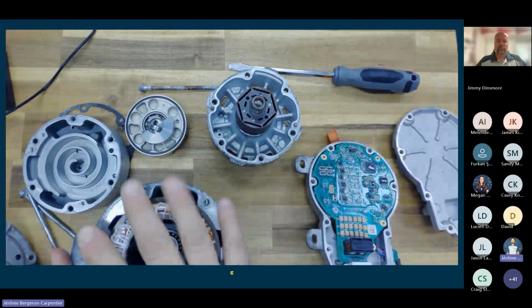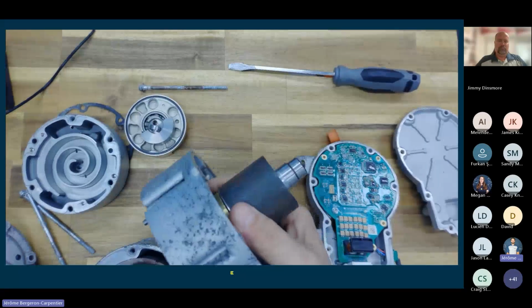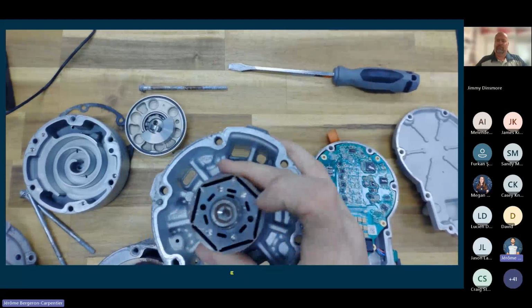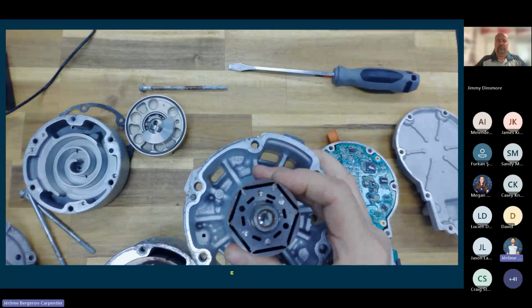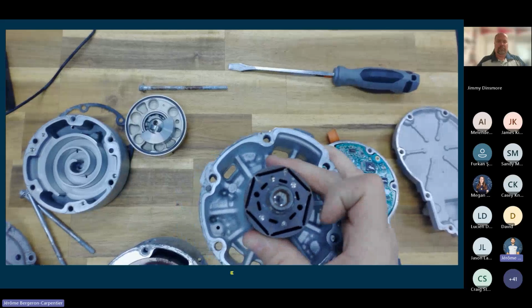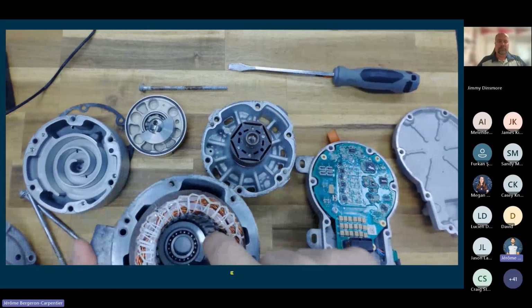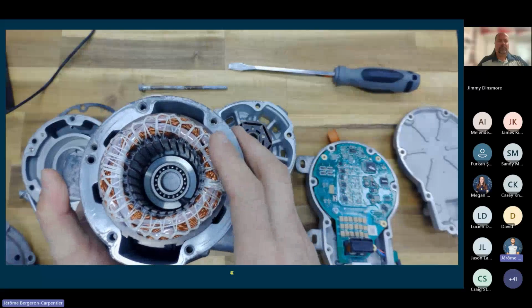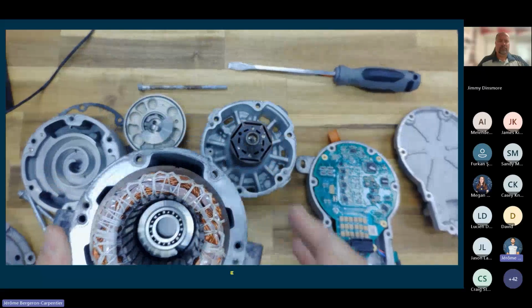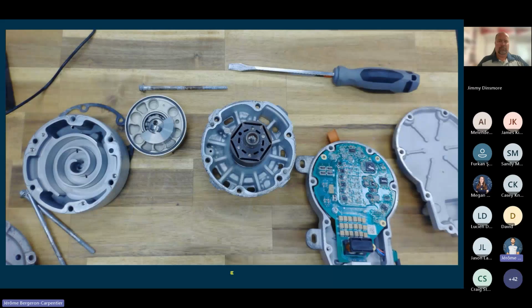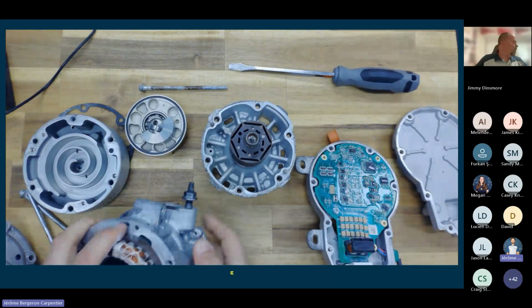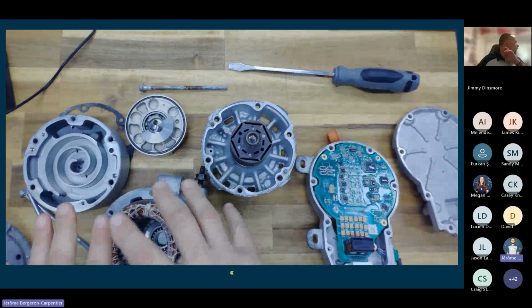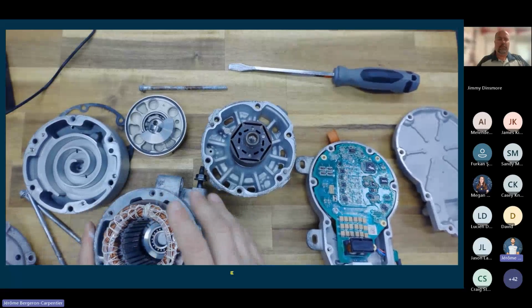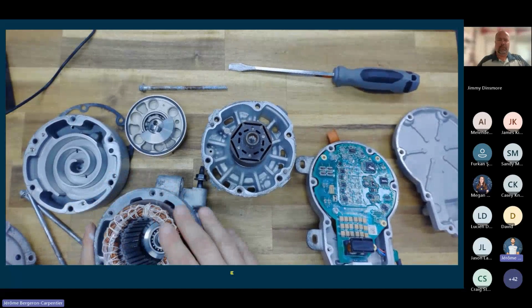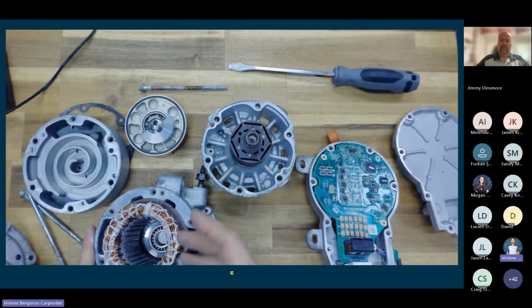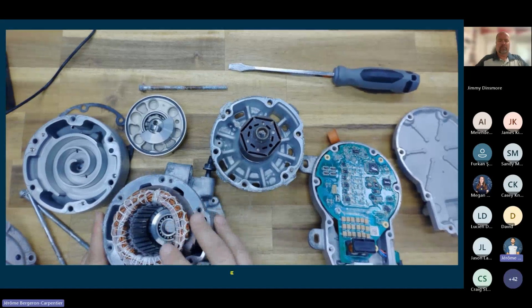So here we go. We've got a standard stator, and we have a permanent magnet rotor. The magnets have been removed, typical neodymium style magnets. You can see it's a 6 magnet rotor, and it's a 27 segment stator. So it's wound 27 times. Most stators are usually around 18. The reason for the extra holes, I guess you could say, inside the stator here is for harmonics. By having more, it smooths it out, less harmonics, less noise inside that compressor itself.